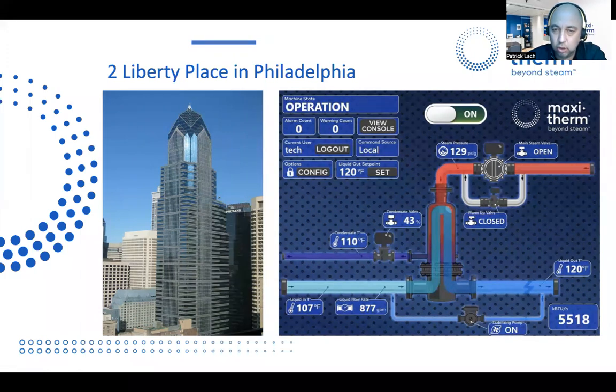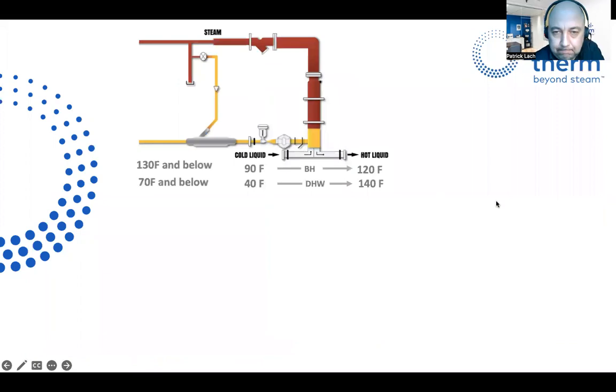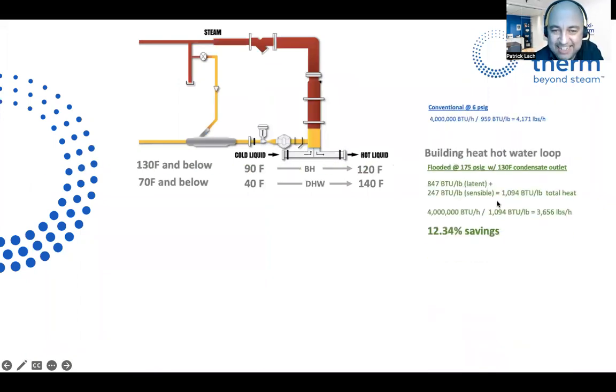Quick things that you see on the screen: we see the actual GPM going through the heater and the actual BTU per hour. You can pull out trends, see how the system is working. Very good for troubleshooting. So again, go on our YouTube channel, you'll find more info on everything. Next slide, please. Okay, you can click through them all, please, Anushka.